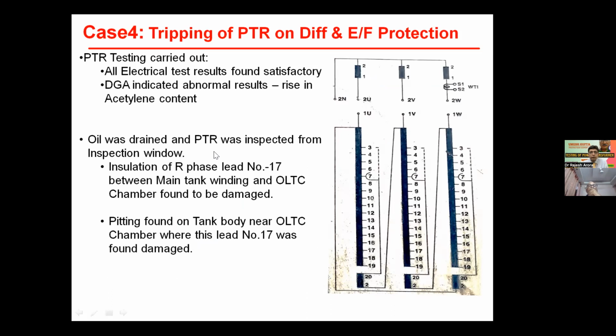So it was decided to drain the transformer oil and inspect from the inspection window. From the top, we couldn't find anything. Thereafter, the oil was completely drained, and from the bottom window, what we found was, in the transformer, apart from the HV main winding, we have some tappings. These tappings are coming from the transformer main HV winding in the form of leads and going into the OLTC chamber. Now for this particular tapping number 17, the lead of R phase, we found that its insulation was damaged near the OLTC chamber point only, and some pitting was also found on the tank. I will show in the next slide.